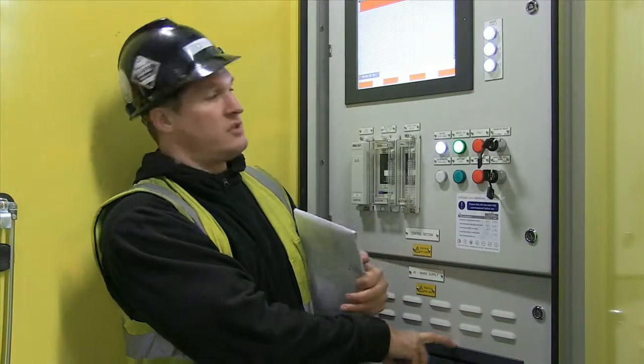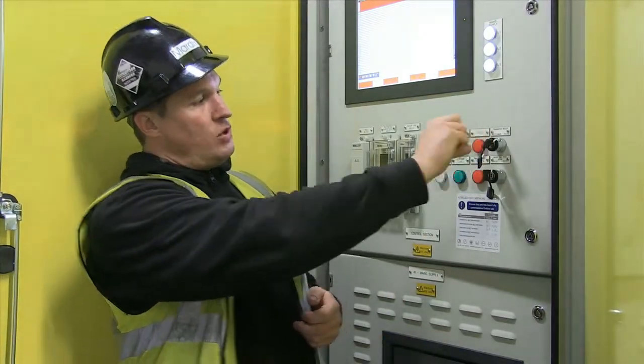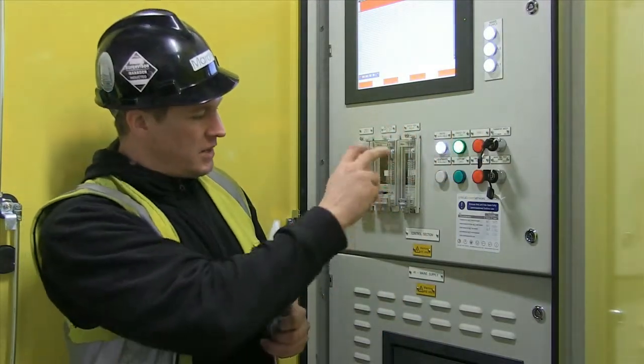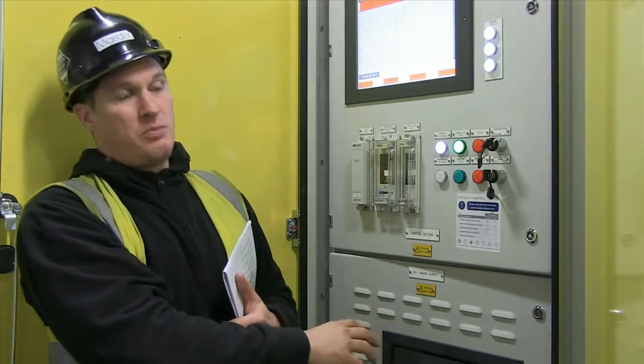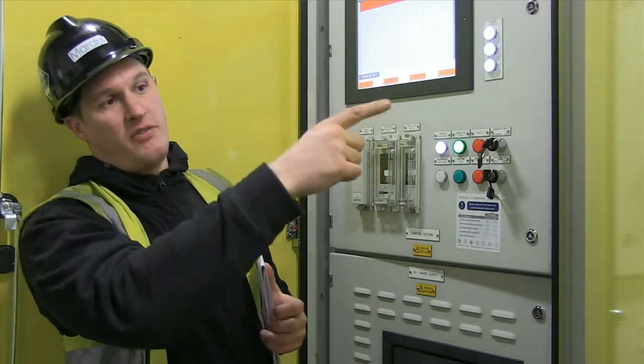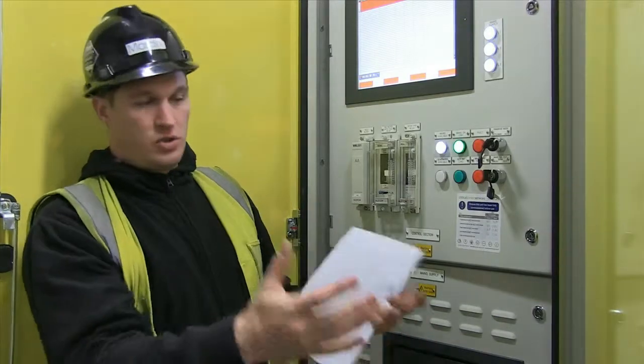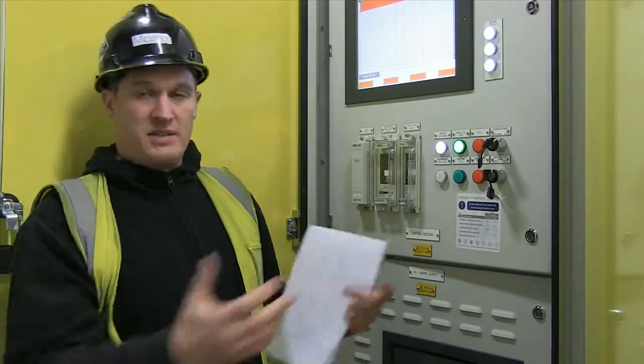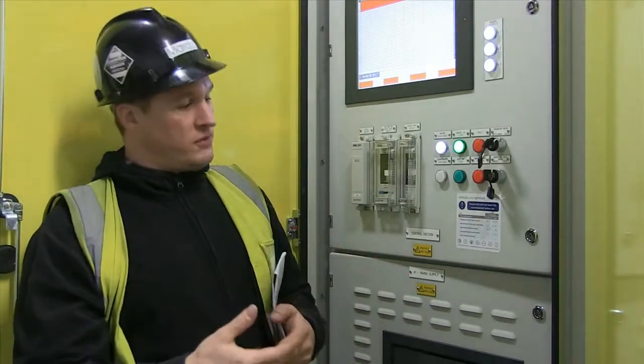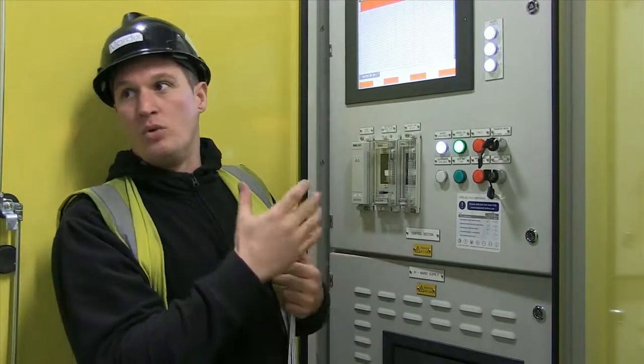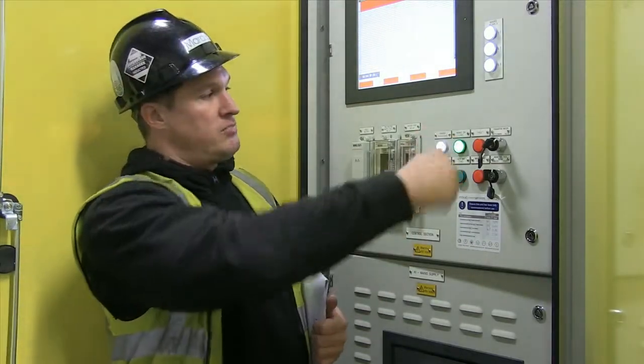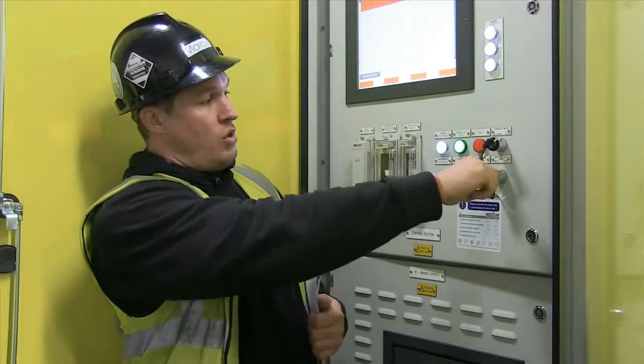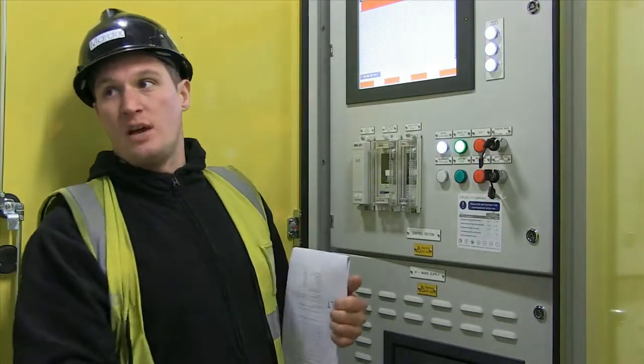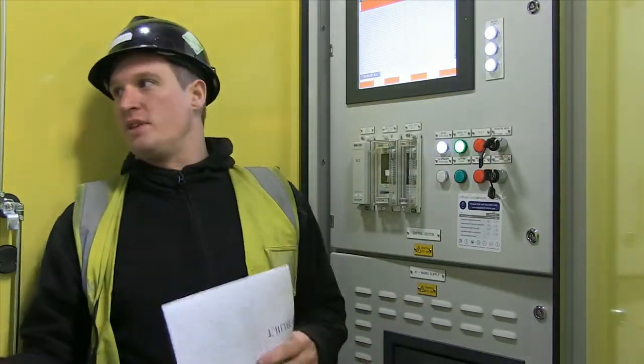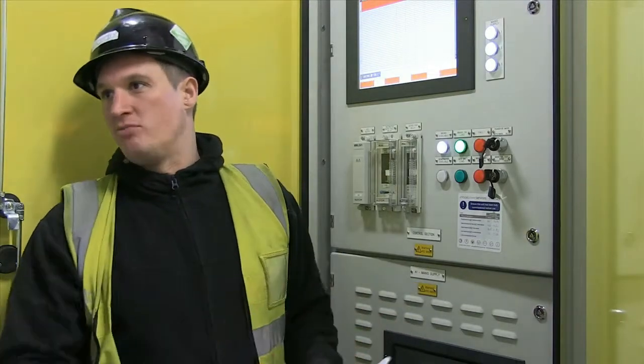within 5 seconds. The difference is, if I put it to auto manual, get mains failure, mains breaker opens, start the generator, generator's confirmed, generator breaker closes, supported on generator. Mains then returns, 5 minutes proves, but nothing will happen. It won't automatically reclose. You'll then have to just manually click it either into auto or click it into reset, and it will reset the Zelio and then it will close. Basically so that you guys have to come and reset it at the panel rather than it just doing it by itself.